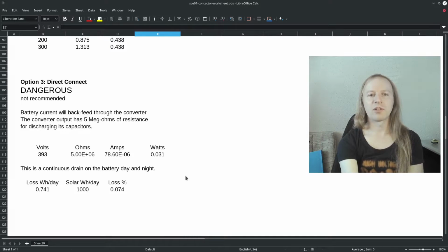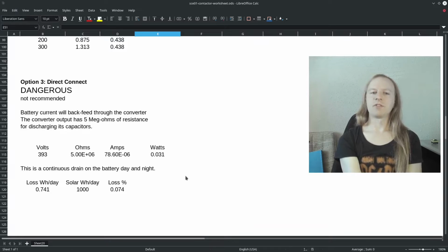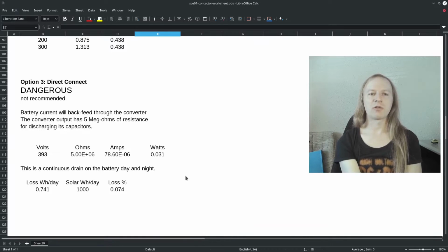Using Ohm's law, 393 volts divided by 5 megohms gives 78 microamps, and we can calculate the power: 0.031 watts, or 31 milliwatts. That's a continuous power drain even during nighttime, so we can calculate that out to a little less than 1 watt-hour per day lost if the charger were connected directly to the high voltage battery.